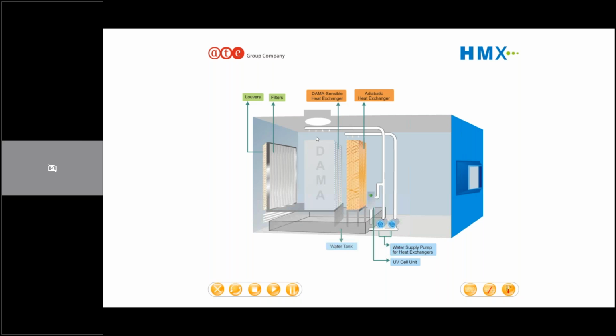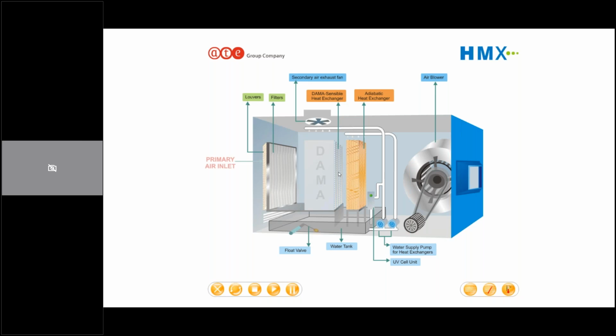So this is the heat exchanger I was talking about, and then there is a subsequent pad for direct evaporative cooling. This has a counterflow heat exchanger. One path is for the supply air going through the system, and one is for the air coming from the bottom, which is then exhausted out. In that exhaust stream, you have a spray of water saturating that air to its wet bulb temperature.